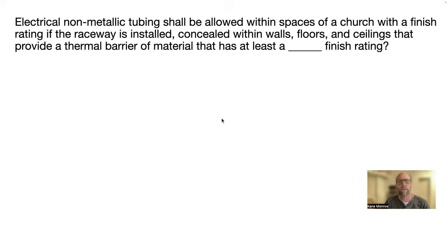Electrical non-metallic tubing shall be allowed within spaces of a church with a finish rating if the raceway is installed, concealed within the walls, floors, and ceiling that provide a thermal barrier of material that has at least blank finish rating. All right, guys. So first off, you may think, oh, we're talking about Smurf tubing up here, which we are. Don't go flipping to Smurf tubing. Go back to 518, which is places of assembly. So those are churches, and you'll find the answer, 15-minute finish rating. So a fire rating of 15 minutes, 518.4 C1.